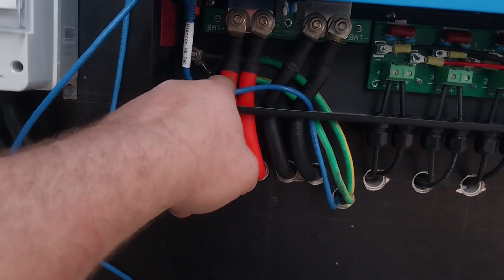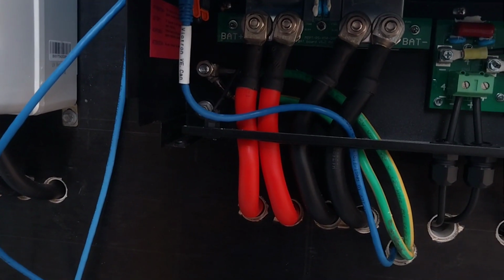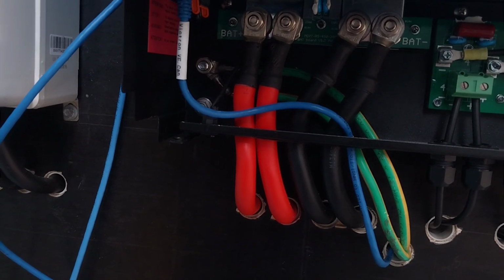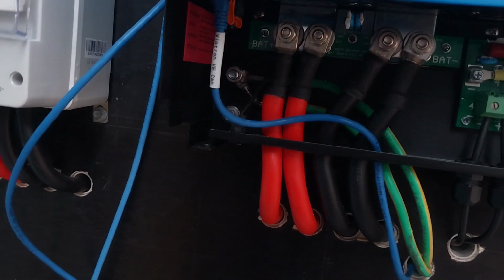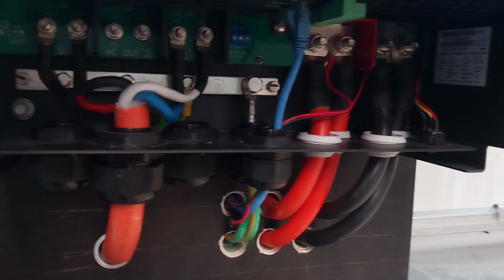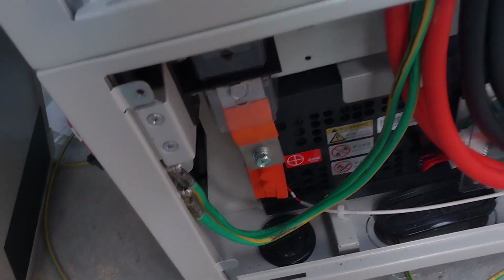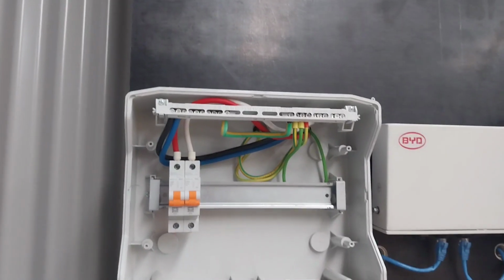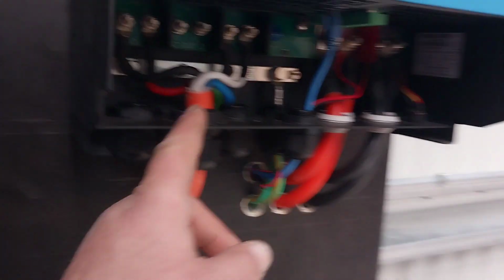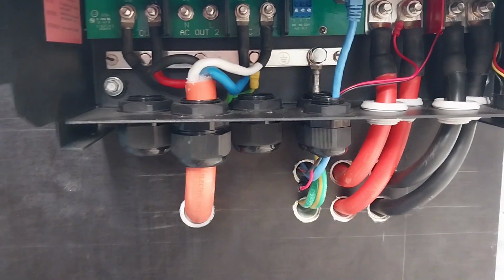Each 16mm is for 50mm cable, because that's what Australian Standard 3000 Table 5.1 wants. So I need two of them because I've got two 50 mils or a single 25 mil earth cable. Same here at this end. There's the hub, very similar to what that's doing for the actual DC cables. And another one down here. That's why I've got 6 by 16 mil all joined here. Not to mention the AC earthing. Obviously anything with an AC supply like the Multi Plus 2 inherently comes with an earth cable in there.